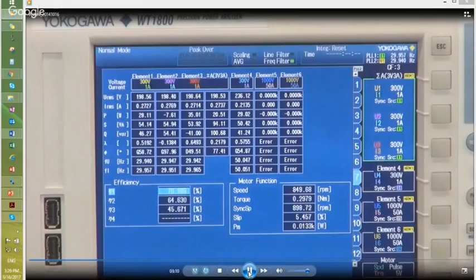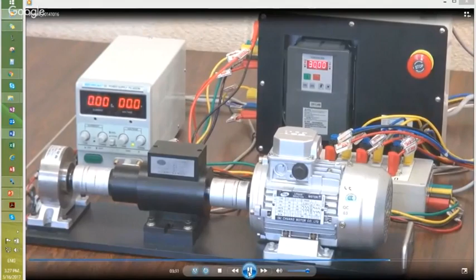Right now this connection is connected to the motor as well as the VFD to calculate the efficiency of the motor as well as the VFD and the total system efficiency. Here you can see the complete display of the independent power elements: voltage, current, power, apparent power, reactive power, power factor, frequency, even though it is pulse width modulated. Here you can see the motor, load, VFD, and power supply to the load, with the VFD running at a frequency of 30 Hz based on the load.